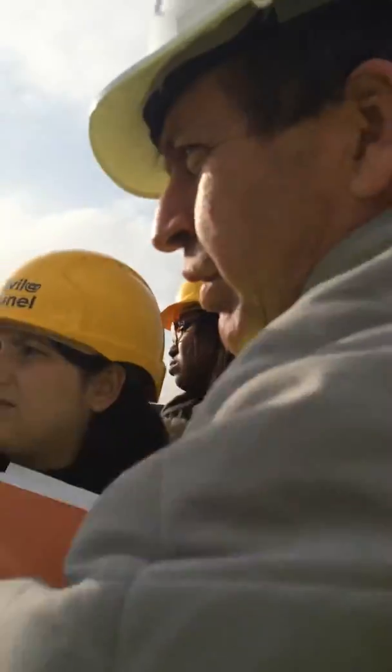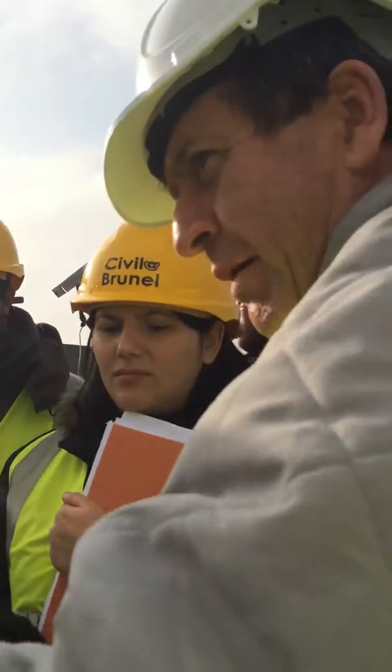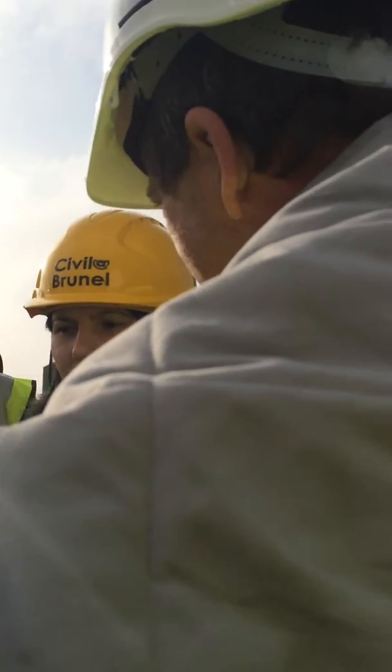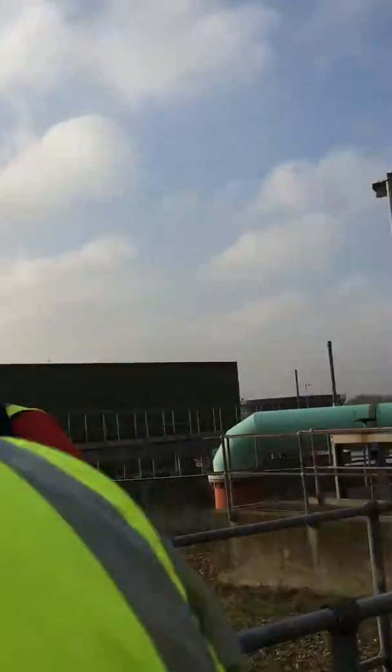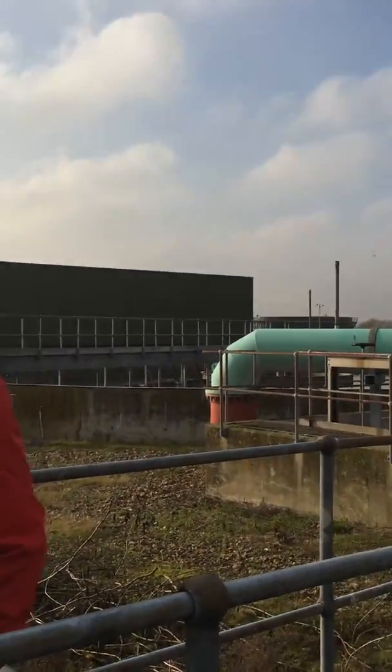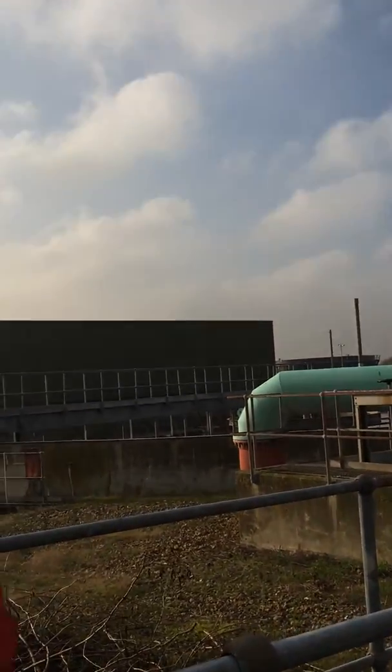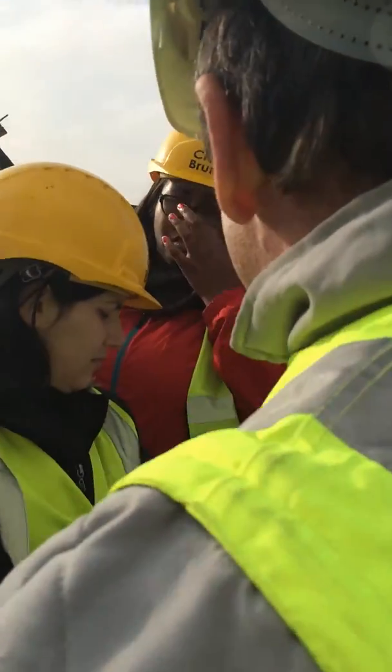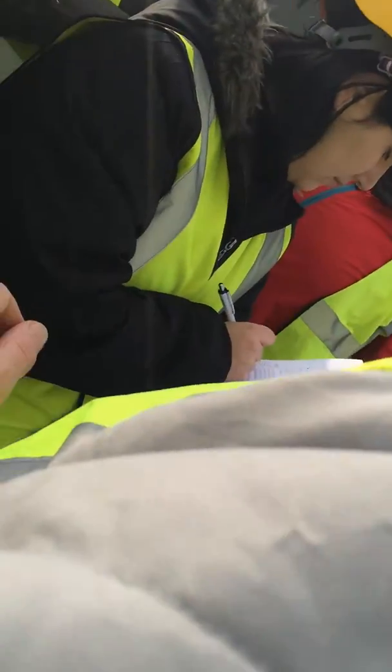So there are rows and rows of air diffusers, but that air has to be compressed because the water depth here is about 5 meters. So we're now having to blow air into the bottom of the tank 5 meters deep. And that building there is where the compressors are to supply the air. It's only at low pressure. The compressors supply air at about 800 millibars or 700 millibars or something in that order. So that's where probably 60 or 70% of all the operating costs of the whole site is electricity consumption for aeration.